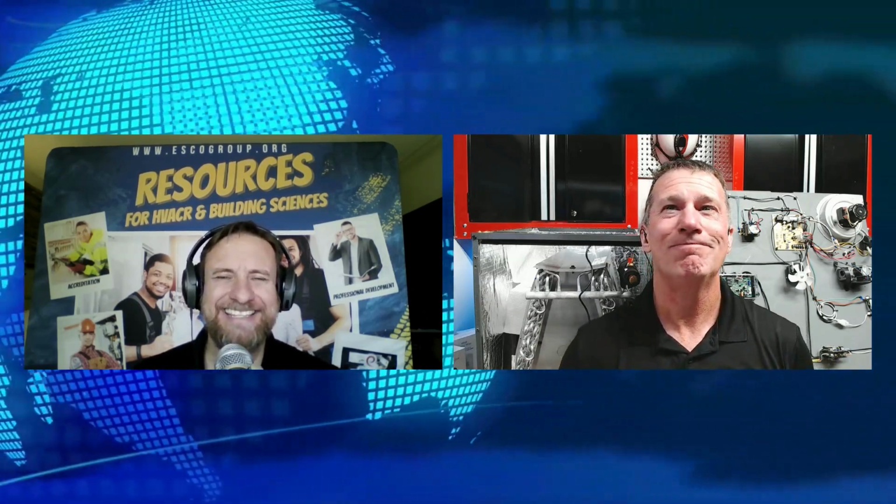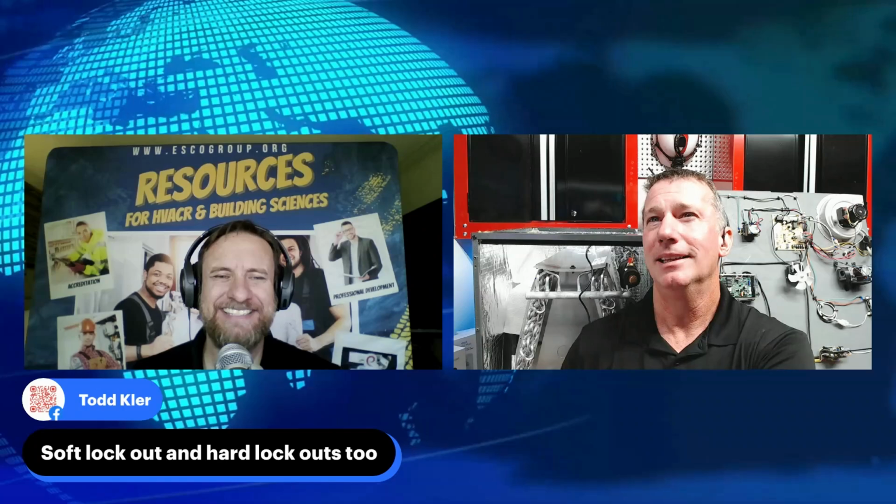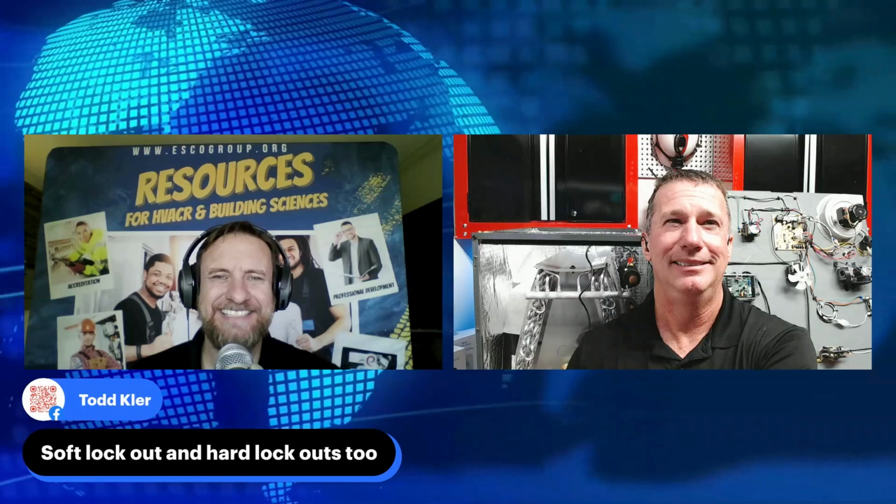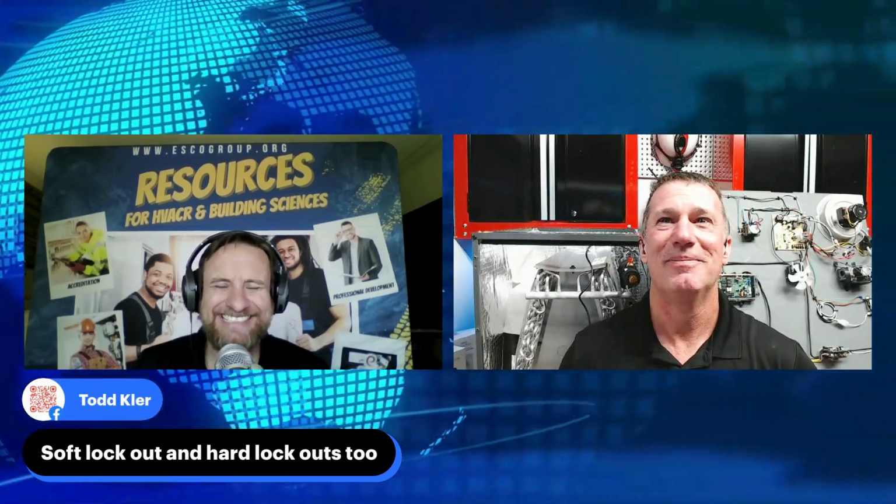Todd, you're exactly right. Now, I want everyone to think about this. Is that soft lockout that we go into a state or is it an action? Think about that. It's not an action, it's a state where a sequence of actions begin. So our control board puts us into a state of soft lockout and initiates a sequence of operation to mitigate the potential for combustion.